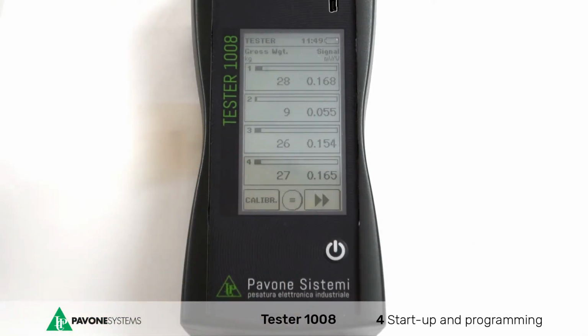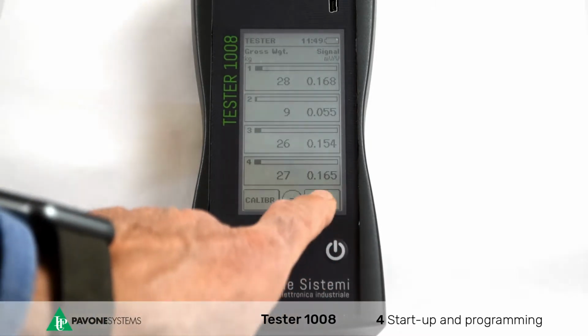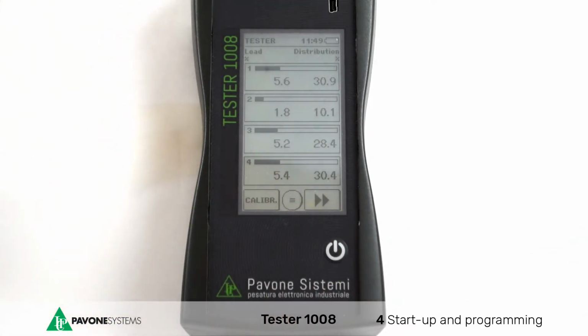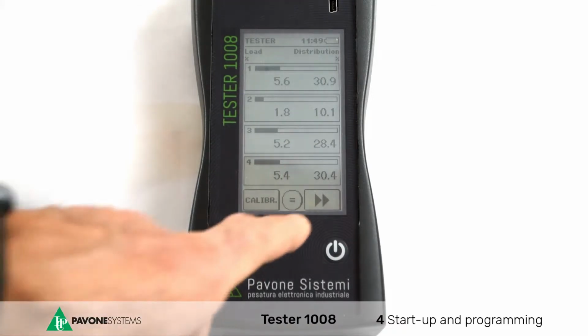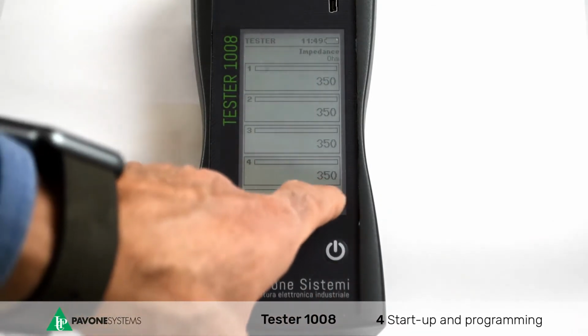Note that the correct values are those expressed in the right-hand column in millivolts per volt, below the signal parameter. If you change screen, you will find the load distribution expressed in percentage. Note that channel number 2 receives a lower load that must be increased. This value has to be between 20% minimum value and 30% maximum value. Now, go back to the main screen.